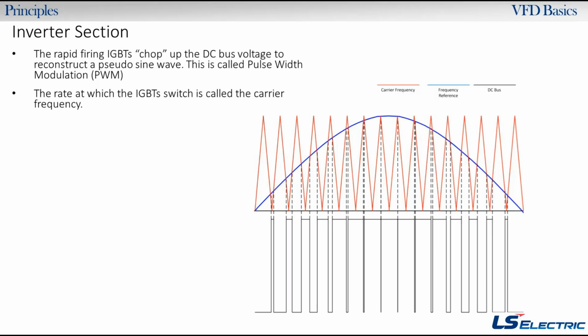So this drawing right here, I feel like it explains a lot, okay? Here's your frequency reference, this blue line. This is like a zoomed in example on an oscilloscope. You wouldn't be able to catch any of these waves with even just a meter, so you zoom in a lot. This is your current frequency reference. Then we have a sawtooth or triangular waveform, this red one. That's your carrier frequency. Let's say you have a carrier frequency of 3 kilohertz, which I believe is the default for most of our drives. That means 3,000 times a second you're going to have these going up and down. That's your carrier frequency. It's like a constant carrier.